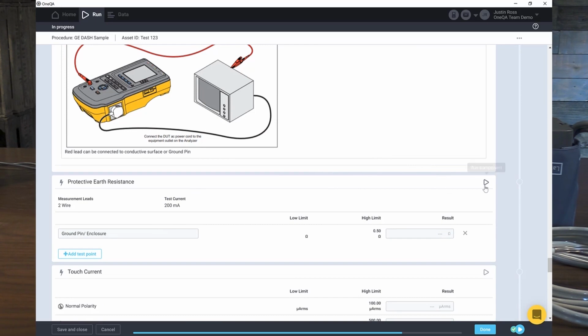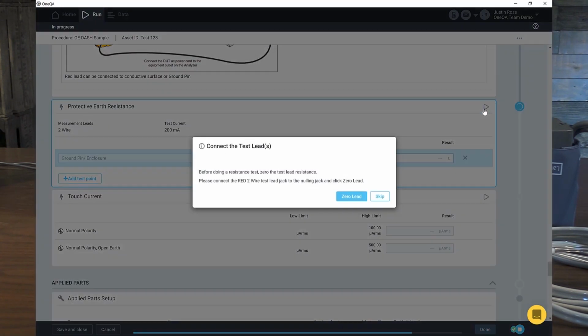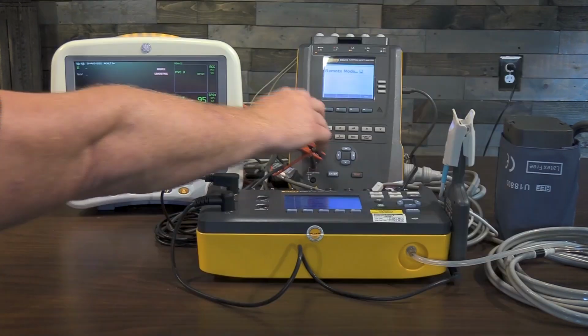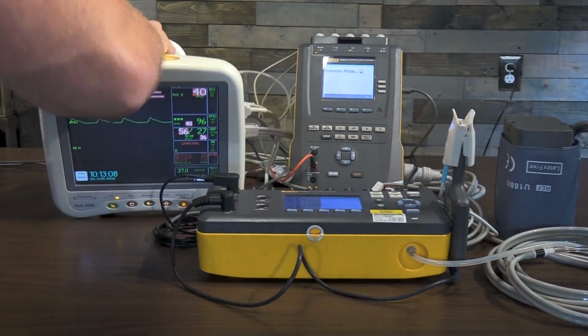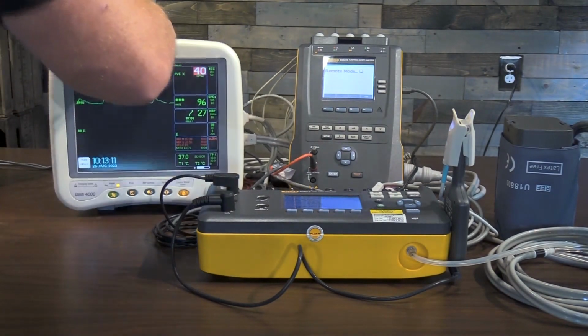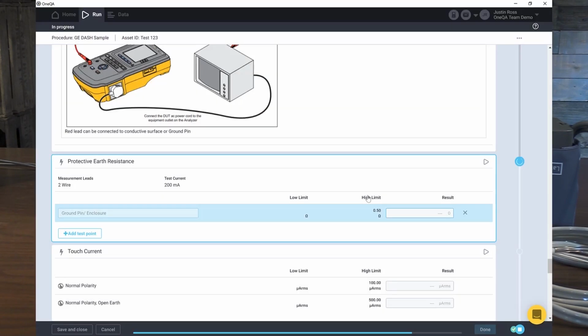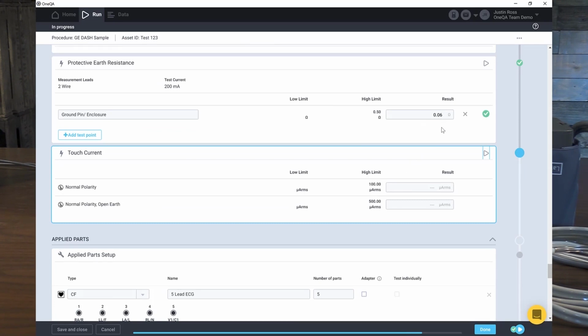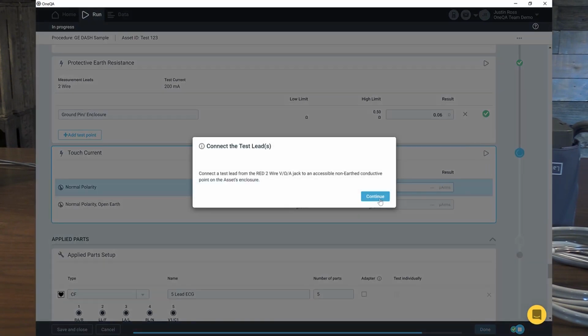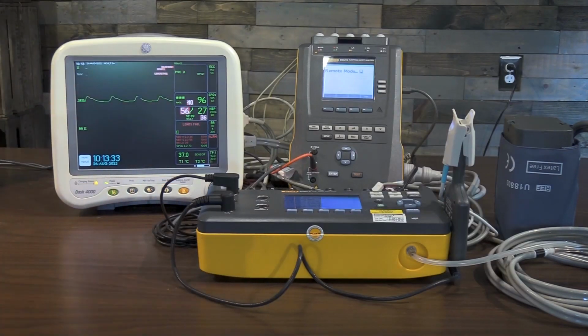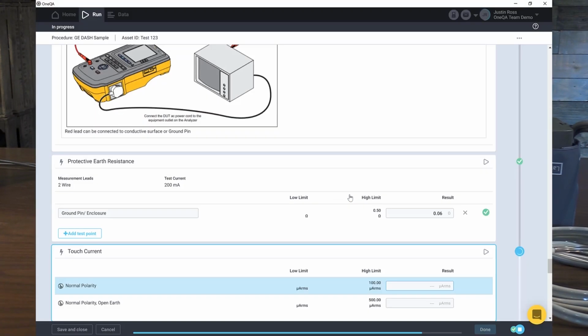So let's go ahead and we'll move down to this electrical safety, and we're going to push run component here. Now it wants me to connect it to my null post, so I'll follow my instructions. We're already connected. We'll zero that out. Now we're going to connect this to that test point that we showed in the prior instructions. All right, and we're going to continue. And again, this might not be the way you do electrical safety. This is just an example. And you see it automatically generated a resistance. Push run on the next one. Continue. Again, I'm not pushing any buttons on the electrical safety analyzer. I'm not adjusting anything. I'm simply hitting run and making sure it's powered on.